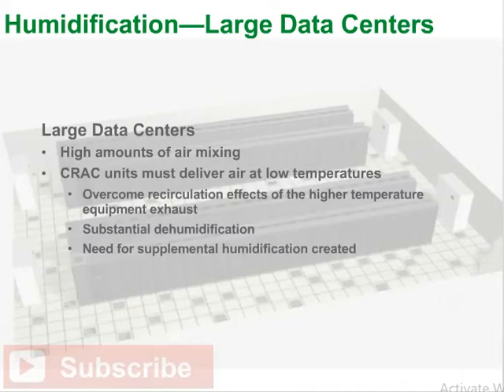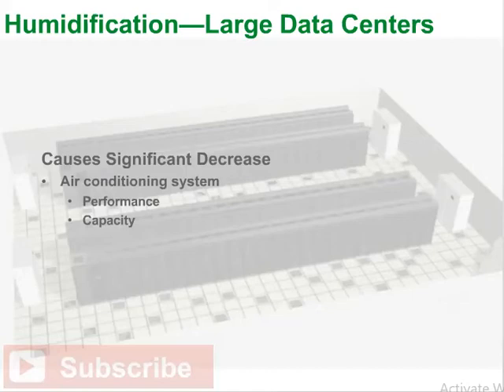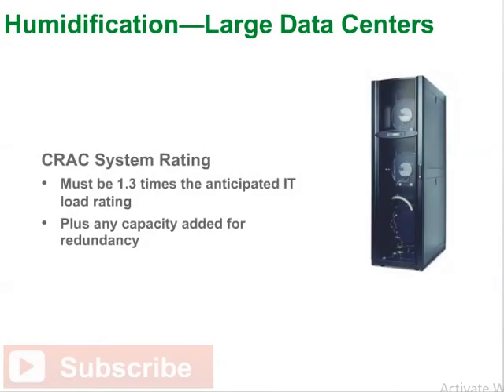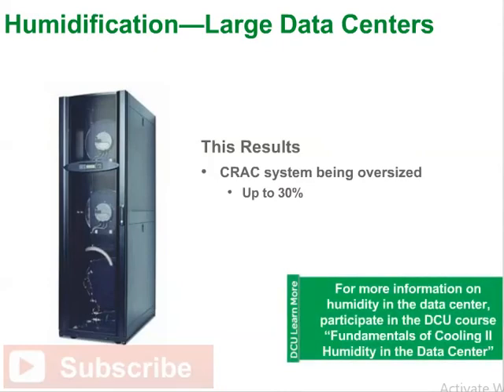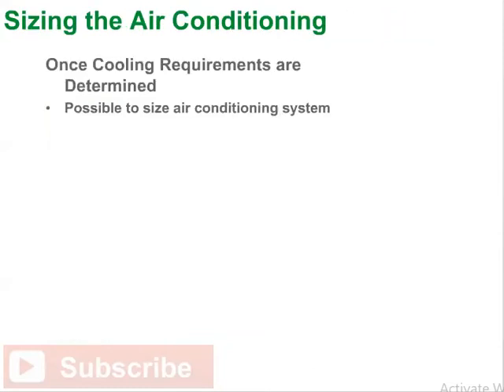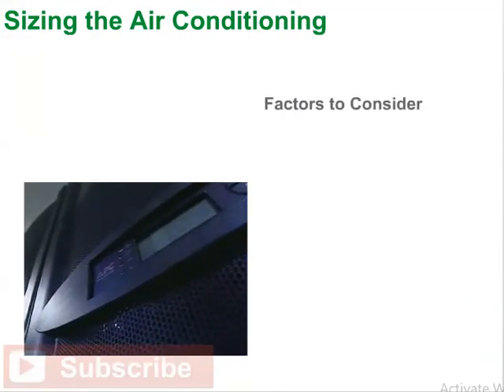For large data centers with high amounts of air mixing, the CRAC unit must deliver air at low temperatures to overcome recirculation effects, resulting in substantial dehumidification and the need for supplemental humidification. This causes a significant decrease in performance. The CRAC system rating must be 1.3 times the anticipated IT load rating plus any capacity added for redundancy. Once the cooling requirements are determined, it is possible to size an air conditioning system.